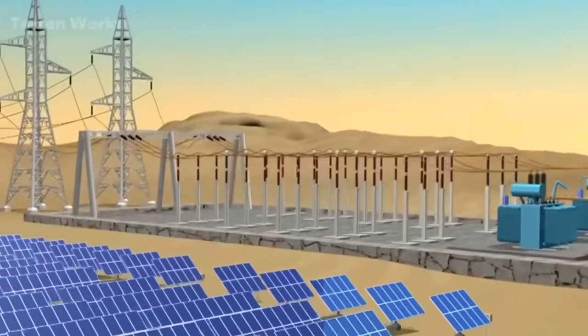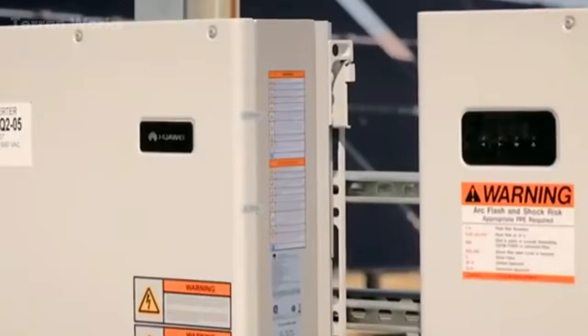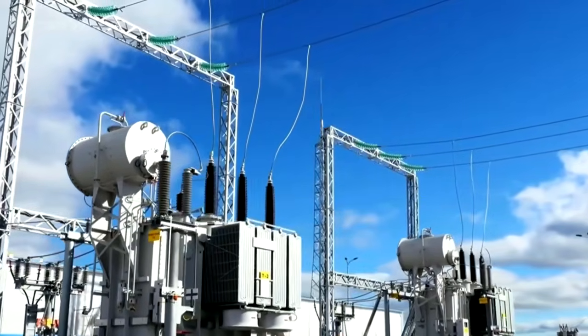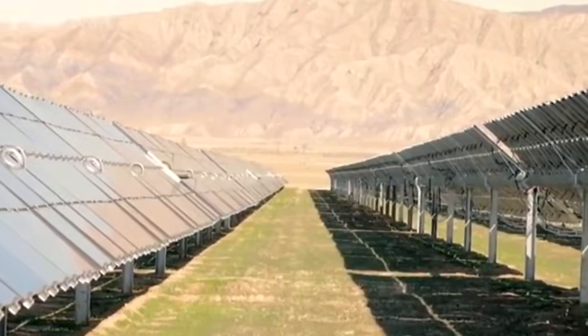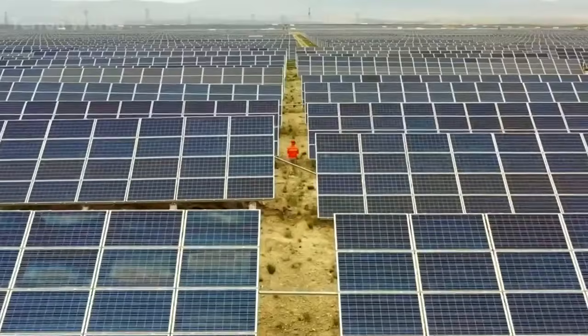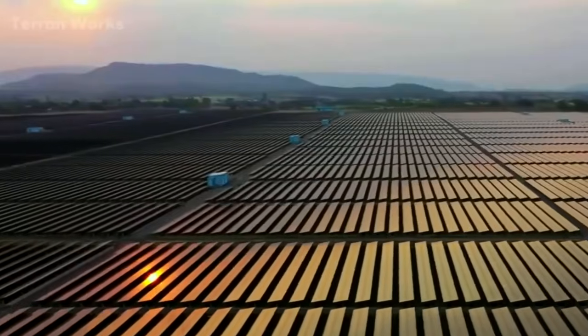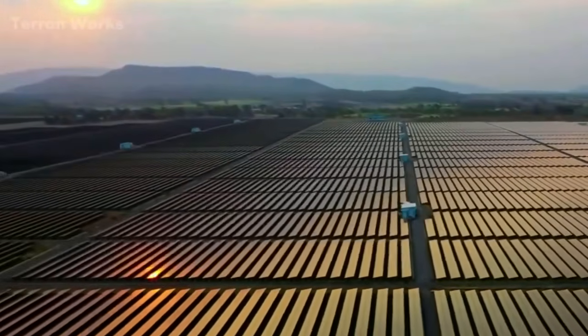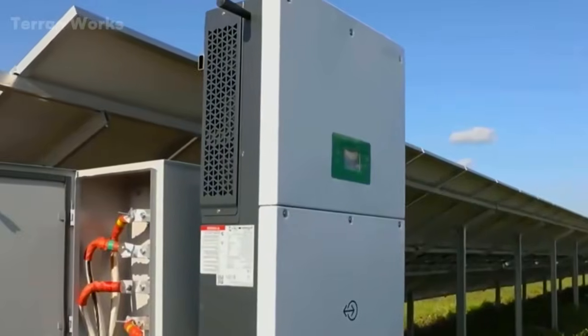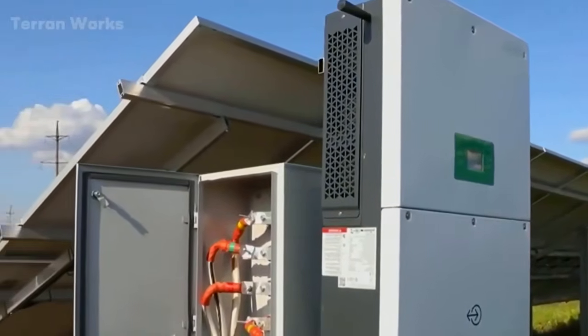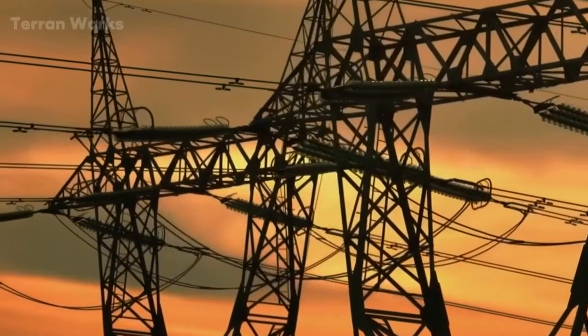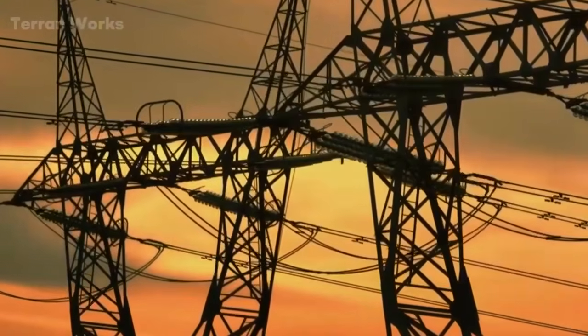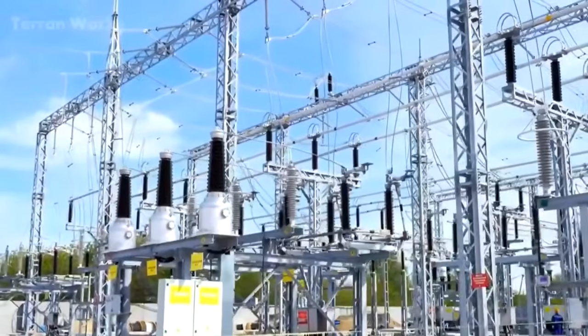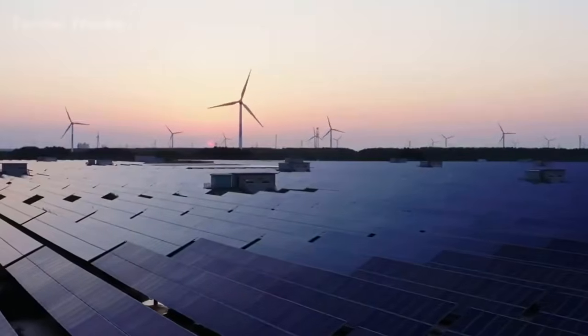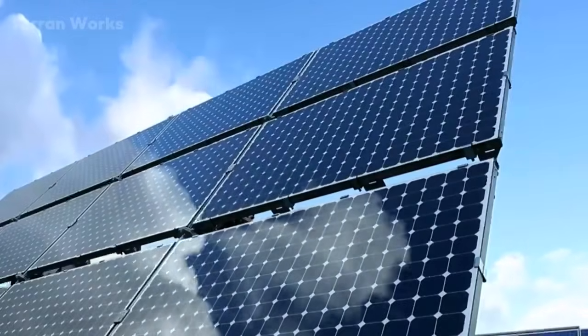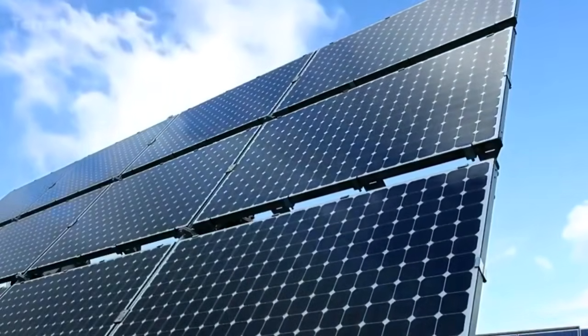With more than 3 million modules secured, the next task shifts from clamps to electrical collection. Each panel produces direct current, while the grid needs alternating current, not usable yet. Crews link dozens of modules into one string, then group many strings into large arrays feeding inverter stations. Cable trays carry the output in controlled circuits because a loose connection can drop a full string. At the inverter station, the tone changes, a low electronic hum, switching clicks, then fan noise. The inverters convert DC into AC matched to China's national grid, which operates at 50 Hz. This step is not optional because the grid accepts power only when voltage, frequency, and phase stay synchronized.